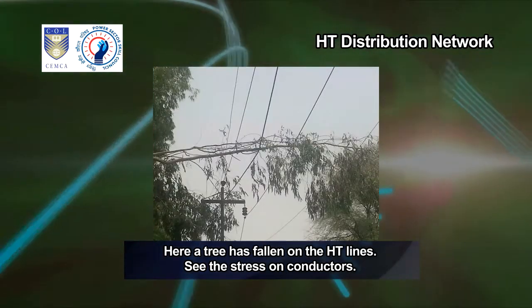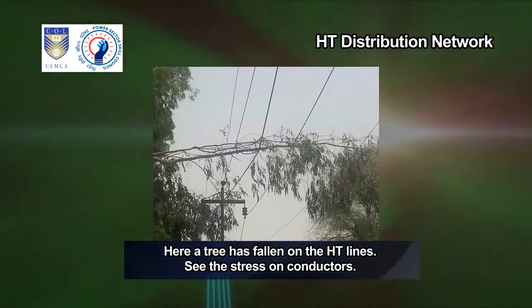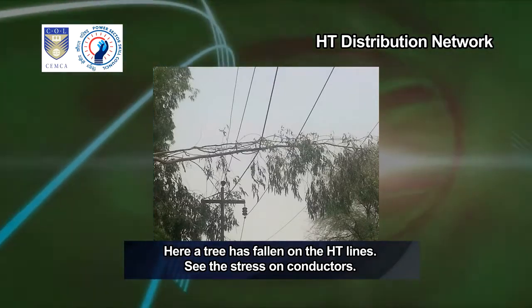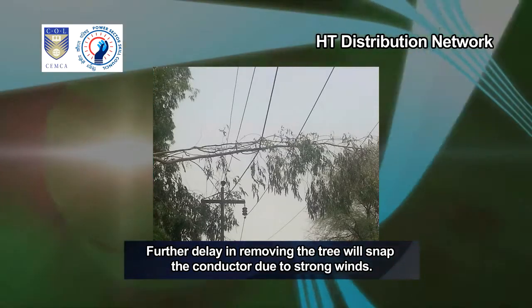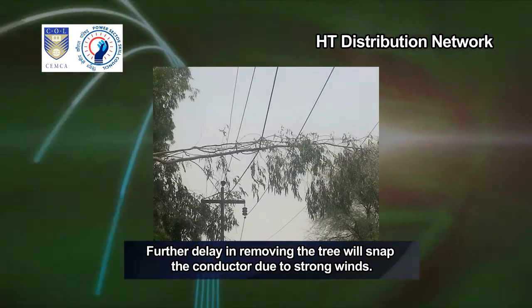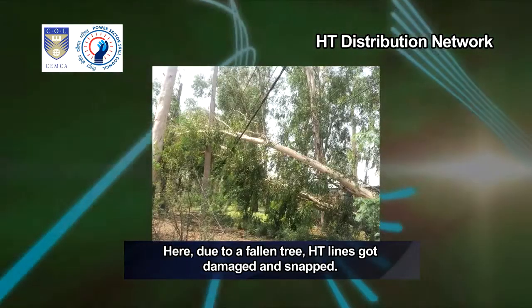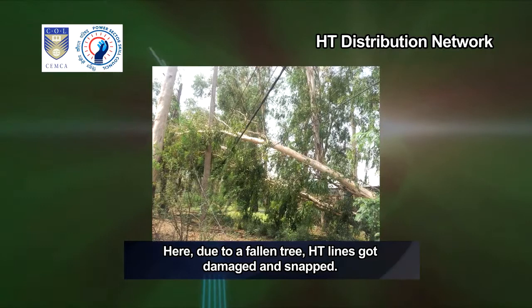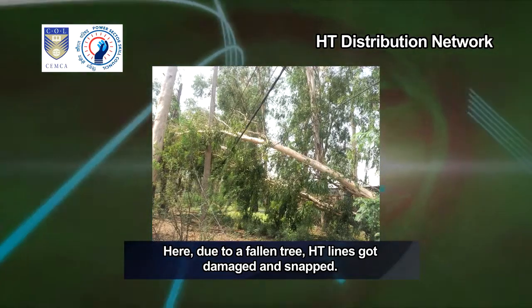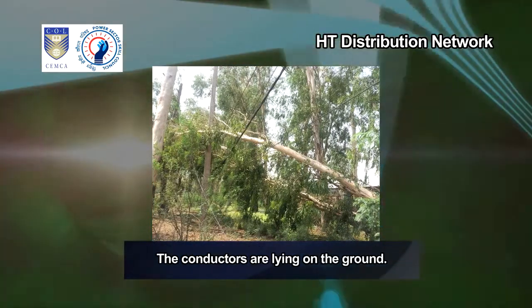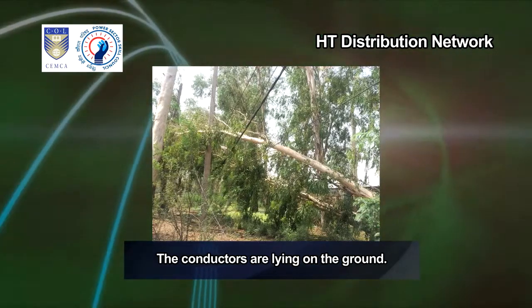Here, a tree has fallen on the HT lines. See the stress on conductors. Further, delay in removing the tree will snap the conductor due to strong winds. Here, due to a fallen tree, HT lines got damaged and snapped. The conductors are lying on the ground.